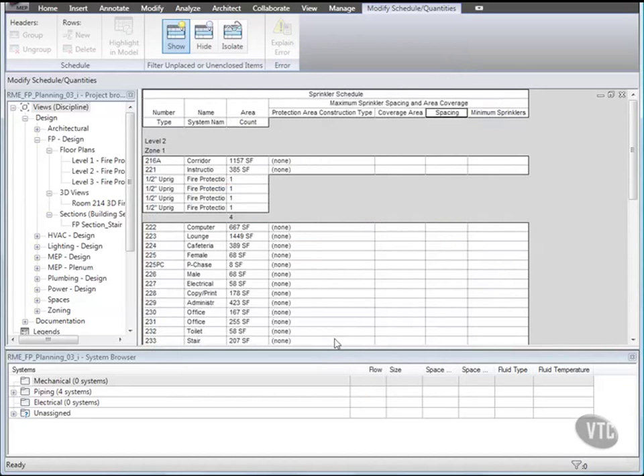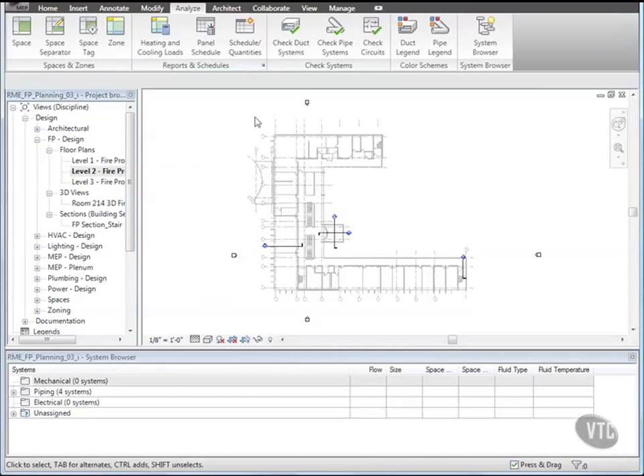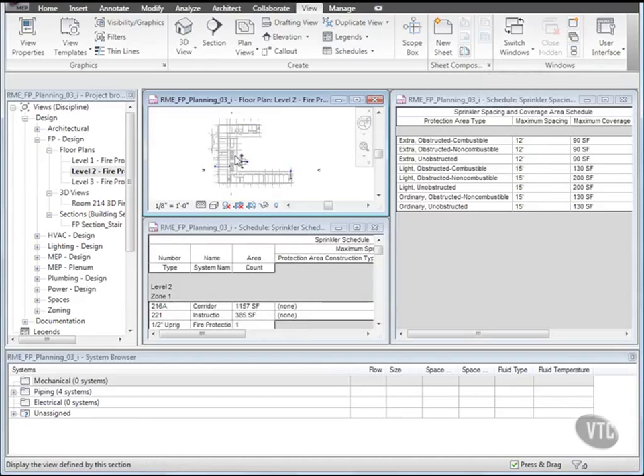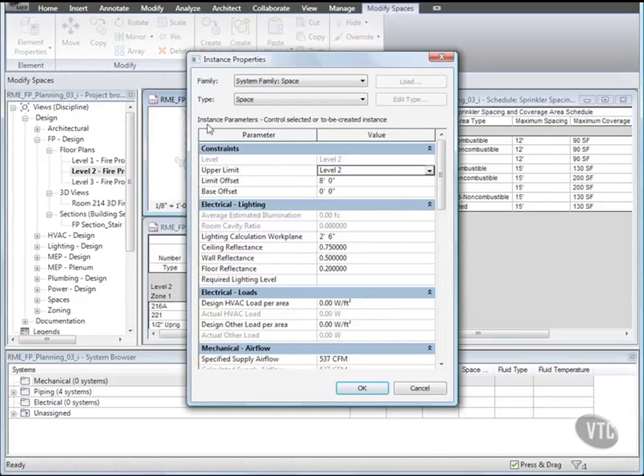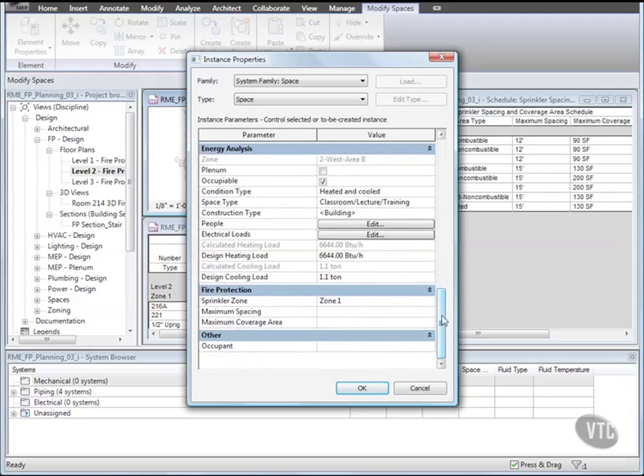Next we'll modify space properties. From the schedule, open the view Level 2 Fire Protection Plan Design. Then click the View tab and from the Windows panel click Tile Windows. Then in the plan view, select Space 221 Instruction and click Element Properties. In the Instance Properties dialog, scroll down to under Identity Data and note that there's nothing specified for Protection Area Construction Type. Then scroll further down to under Fire Protection and notice that the Maximum Spacing and Maximum Coverage Area parameters that you created are listed but their values are not determined. Click Cancel.